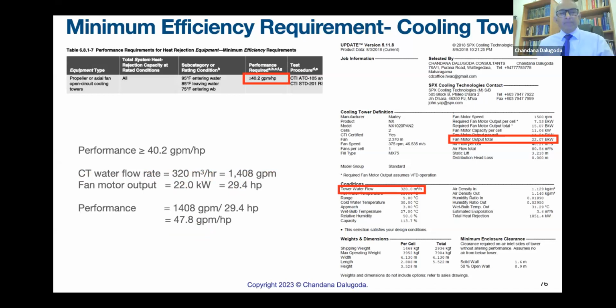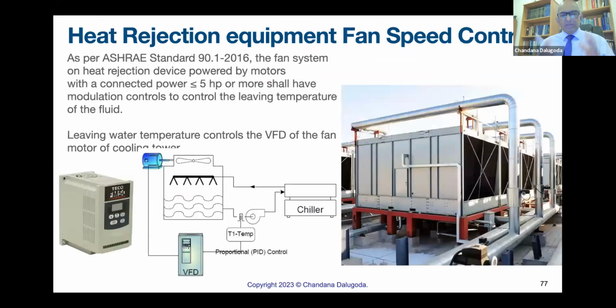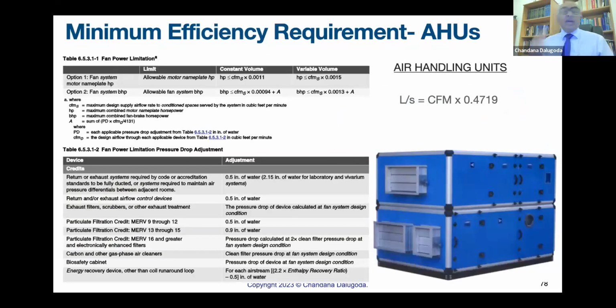We are supposed to have multiple fans with a VFD. If the fan motor is 5 horsepower and above, we must have a VFD with some temperature controlling to reduce power consumption. And AHUs, you have a power limitation. It is given as supply air CFM multiplied by 0.0015 for variable volume, and for constant volume, supply CFM times 0.0011. That value should be equal to your horsepower.